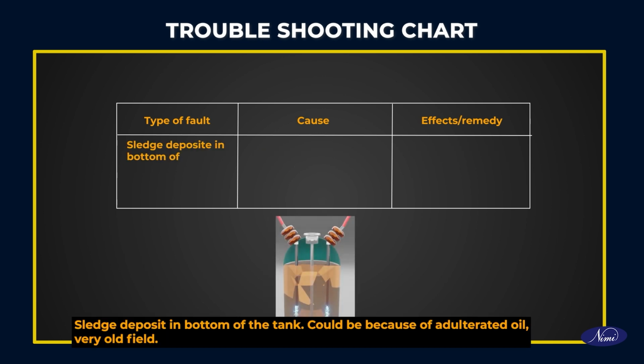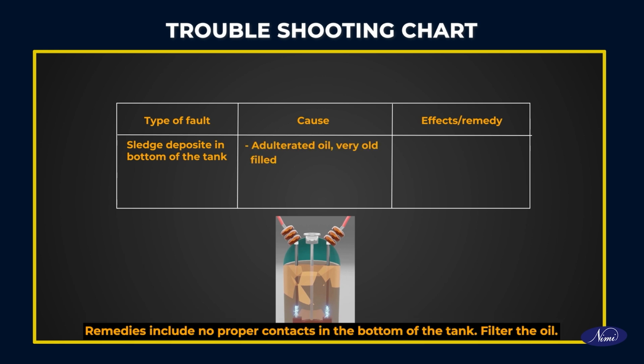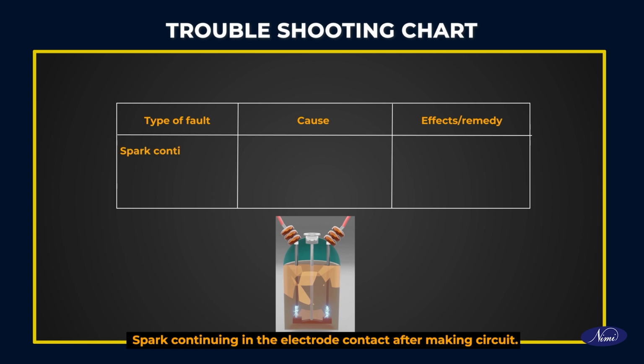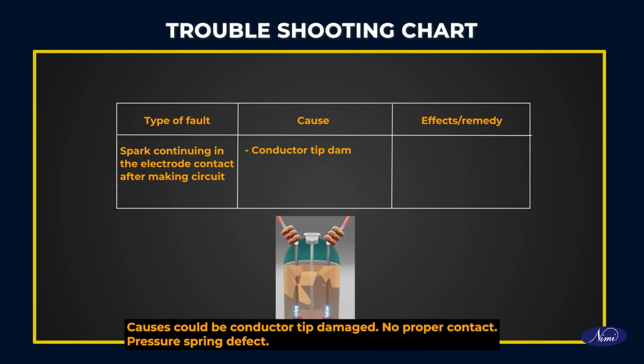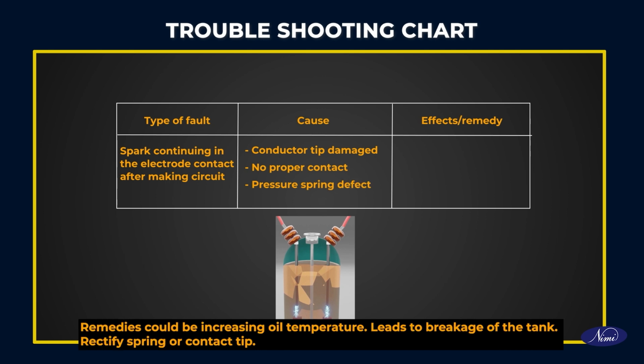Sludge deposit in bottom of the tank. Could be because of adulterated oil, very old fill. Remedy: filter the oil. Spark continuing in the electrode contact after making circuit. Causes could be conductor tip damaged, no proper contact, pressure spring defect. Effects could be increasing oil temperature, leading to breakage of the tank. Remedy: rectify spring or contact tip.